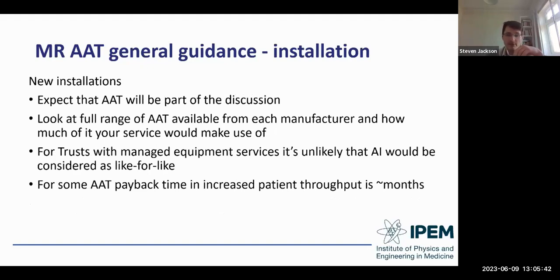For upcoming scanner installations, you can absolutely expect AAT to be part of the discussion. We advise looking at the full range of AAT available from each manufacturer and how much your service would make use of it. There's no point buying, for example, an SMS license available only for 3T brain imaging if that's not something your site does regularly. A note of caution for trusts with managed equipment services: it's unlikely AI will be considered like-for-like. For some AAT, payback time in increased patient throughput is on the order of months, so the business case to add these licenses to a new installation will definitely be worthwhile.